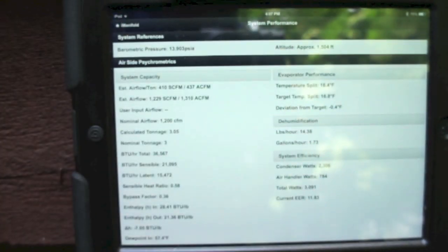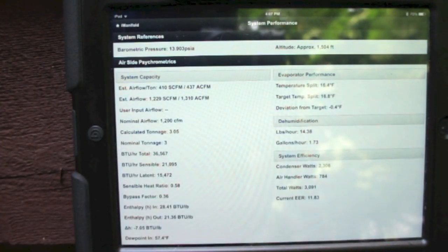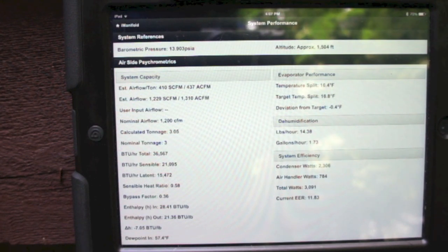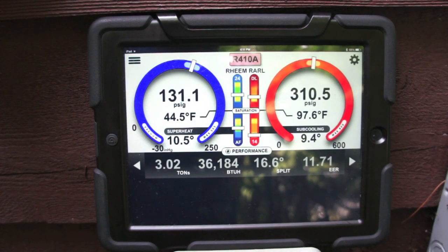So again, you can see how quickly we can do this now because I'm not inside taking 10 minutes, 15 minutes to do a duct traverse and calculate airflow. Simply wireless probe in the supply, wireless probe in the return, power up the iManifold, and we are good to go. Alright, so now that we have everything settled out here, you can see that we are doing 3 tons of cooling and 36,514 BTUs at a 16-degree temperature split, which is exactly what the split should be as it was calculated, at 11.81 EER.